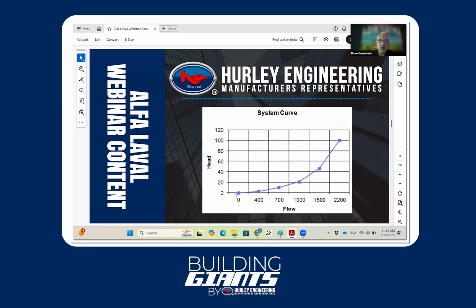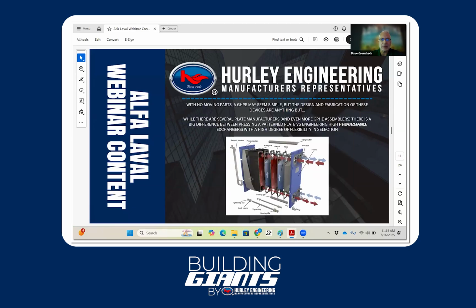This image shows a system curve: as you increase flow, the water pressure drop will increase as well, but exponentially—x squared versus linear. So you don't want to overpump. With gasket plate heat exchangers, it's a balance between going fast enough versus not too fast.